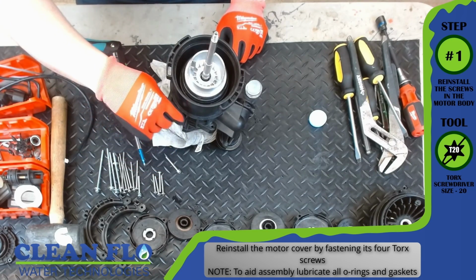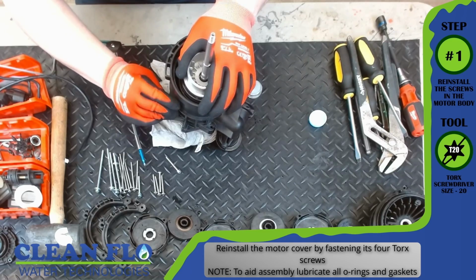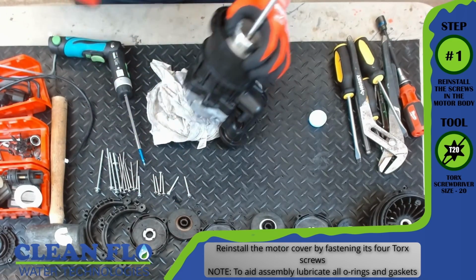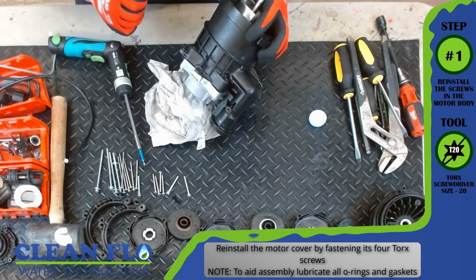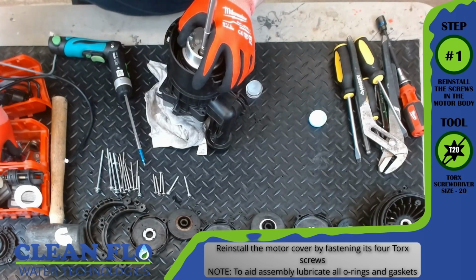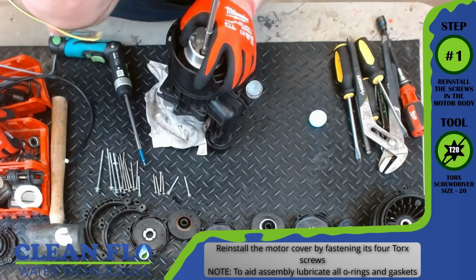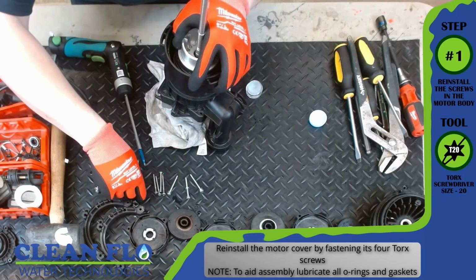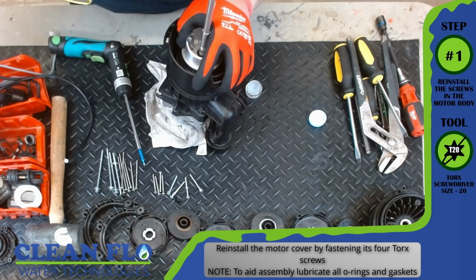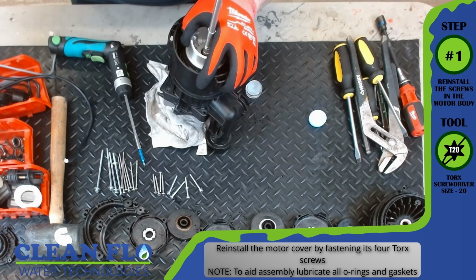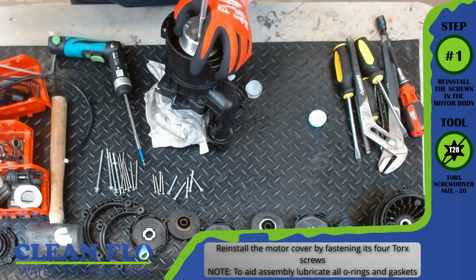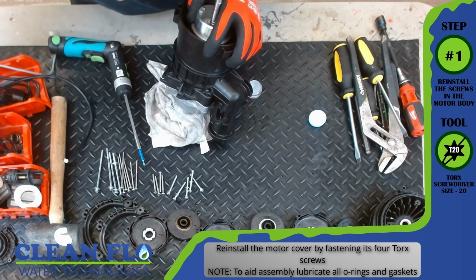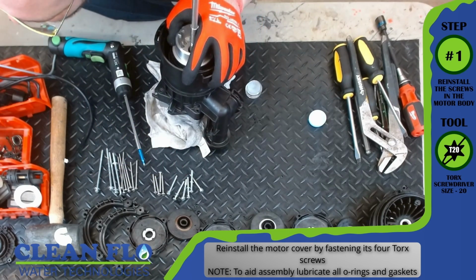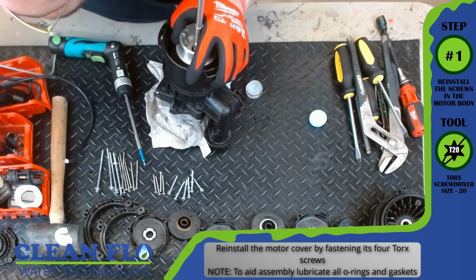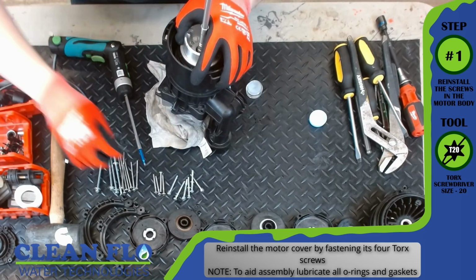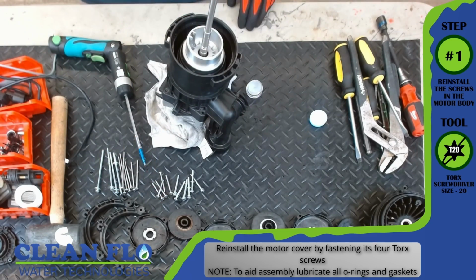By screwing in a crisscross fashion and slowly, the screws can actually pull the pump body down onto the O-rings for proper placement. Be sure not to tighten one side at a time and to slowly go around in a crisscross fashion so things are tightened evenly and there's an even distribution as the assembly occurs.